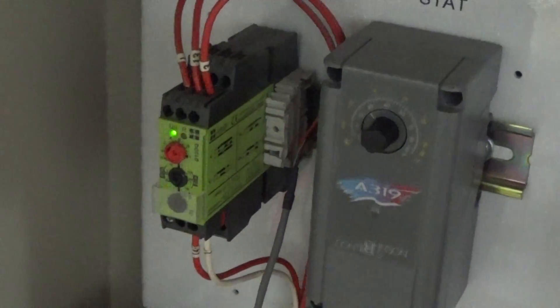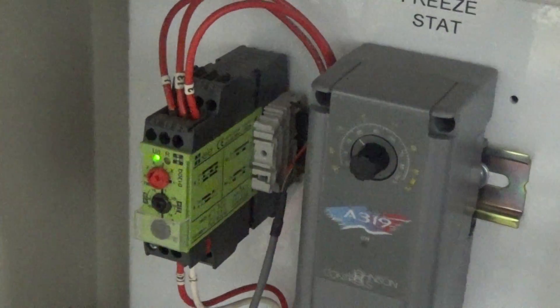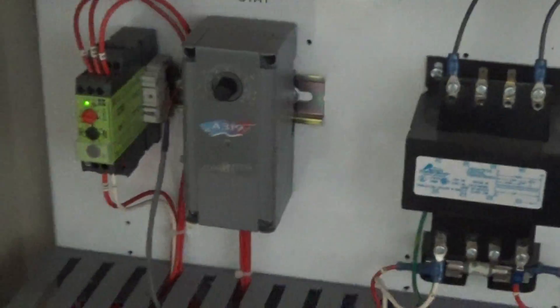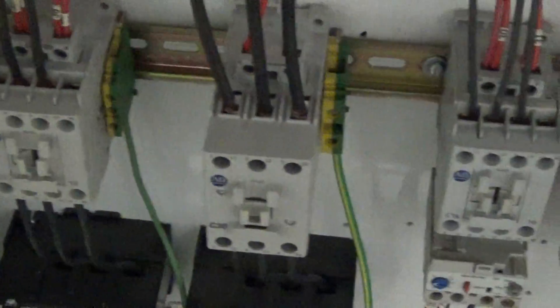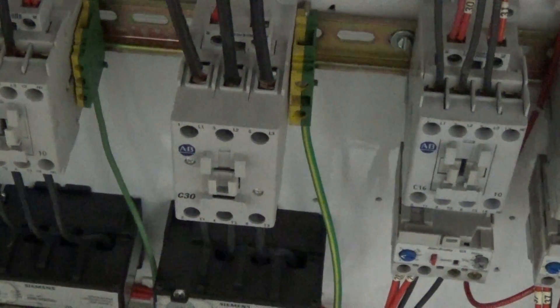This is the inside of our cabinet here. We have a freeze stat and we have the phase detection, which is nice so you can't start this unit up in the wrong phase — it'll go into alarm. Here are our contactors. We actually got two brand new contactors: one for the 10 horsepower compressor and one for the 15 horsepower compressor.